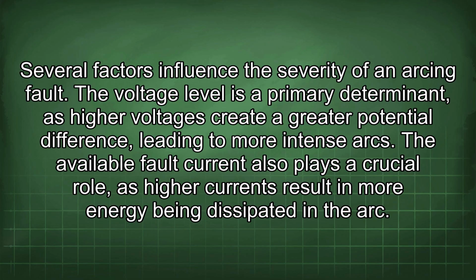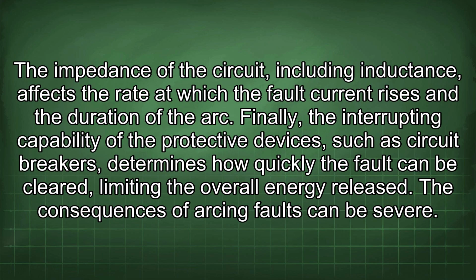The voltage level is a primary determinant, as higher voltages create a greater potential difference, leading to more intense arcs. The available fault current also plays a crucial role, as higher currents result in more energy being dissipated in the arc. The impedance of the circuit, including inductance, affects the rate at which the fault current rises and the duration of the arc. Finally, the interrupting capability of the protective devices, such as circuit breakers, determines how quickly the fault can be cleared, limiting the overall energy released.